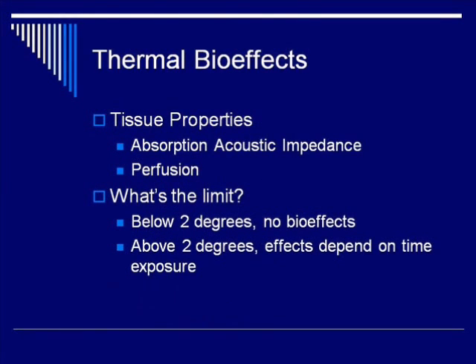Finally, let's discuss two tissue properties: absorption or acoustic impedance, and perfusion. Absorption or acoustic impedance refers to whether the tissue is bone or kidney — the more acoustic impedance it has, the more it will absorb. Perfusion is the blood supply. The more blood you have washing into an organ, the more heat it will be able to wash out — it's kind of like air conditioning for the cells. But there's a limit: according to fetal studies, the fetus being the most sensitive area for thermal bio-effects, so long as you keep the local heating below 2 degrees, you will have no bio-effects. If you go above 2 degrees, the amount of bio-effects will depend on the time of exposure.